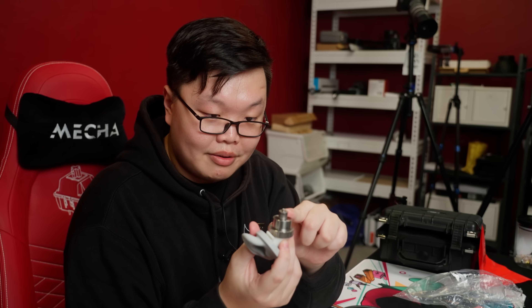The problem now is that I need a preamp, which they didn't give me — they told me I could plug it in directly and it would be fine. Clearly, that's not the case. You definitely need a preamp. This is clearly not a BNC connection. The other interesting thing is that because of the shape of the ear canal, you can attach this adapter, which is used for mostly sound and volume calibration. So if you have a 94 dB SPL test meter, you attach it to this and it calibrates accordingly.